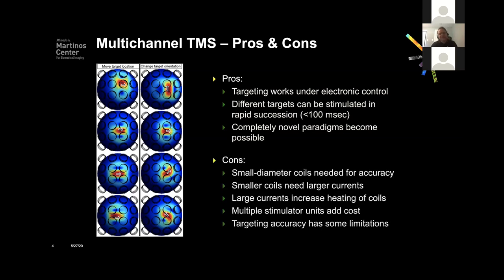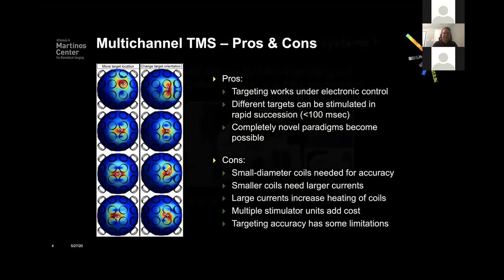There are always trade-offs in this approach. If you start building smaller coils, you need more current to stimulate the brain, and the larger currents result in more heat dissipating in the coils. You need multiple stimulator units, which adds cost. The targeting accuracy also has some limitations because we use the degrees of freedom offered by these 16 channels to shift the target around and shape the field, so there are limitations on what you can do.